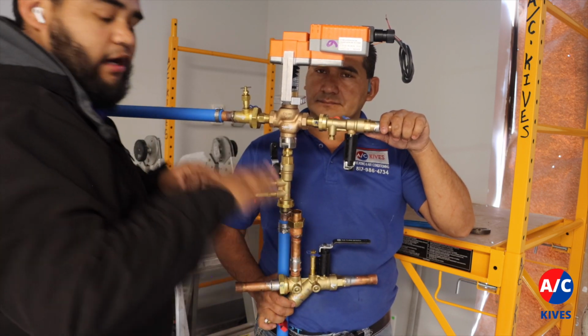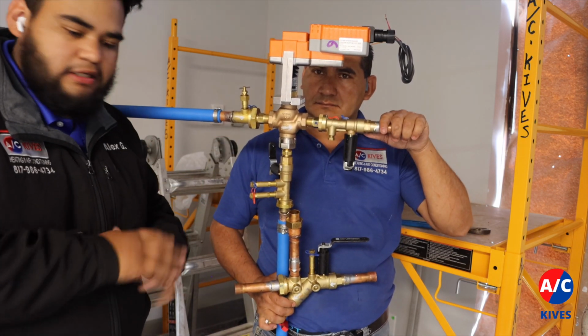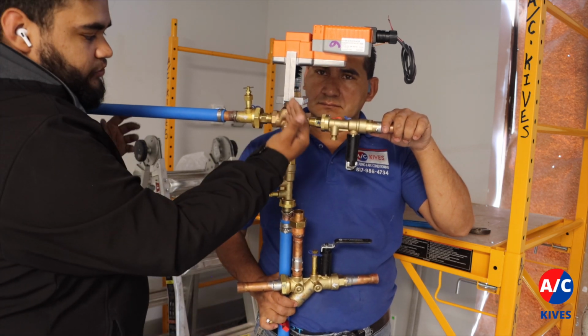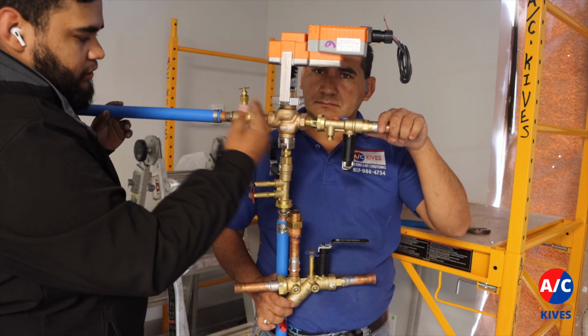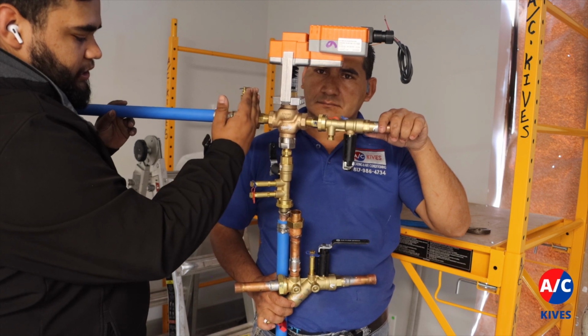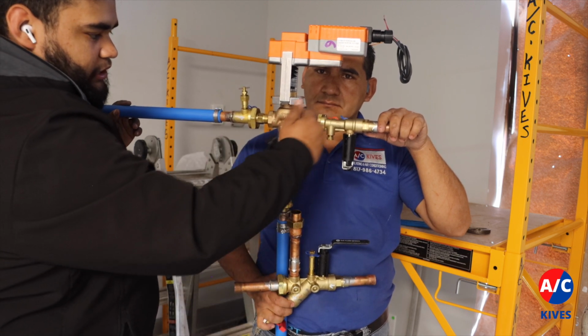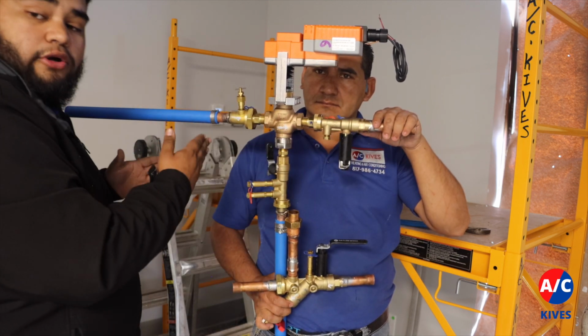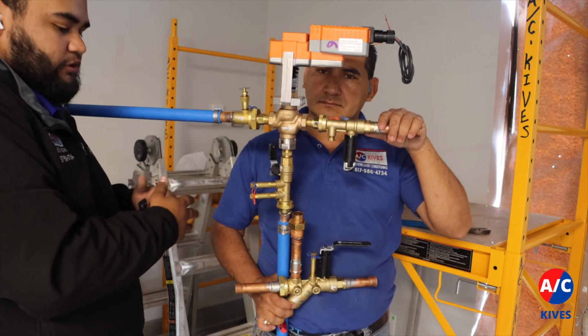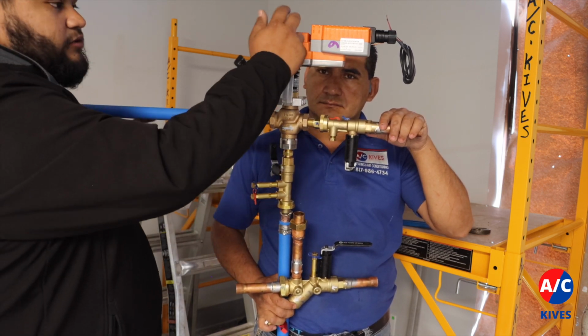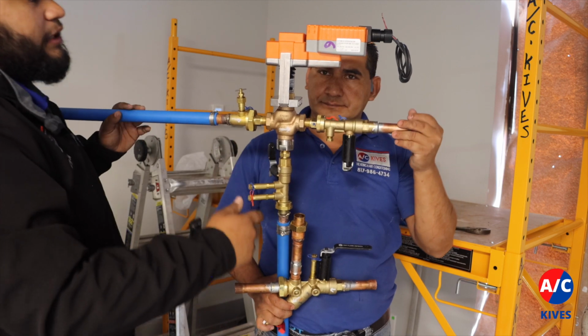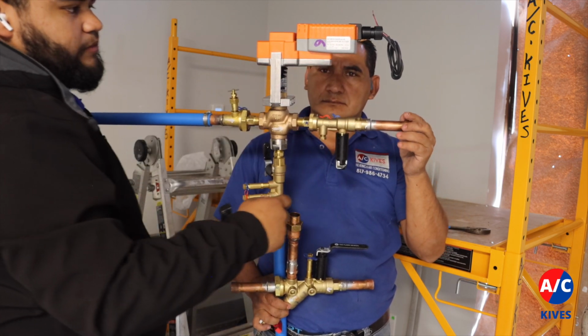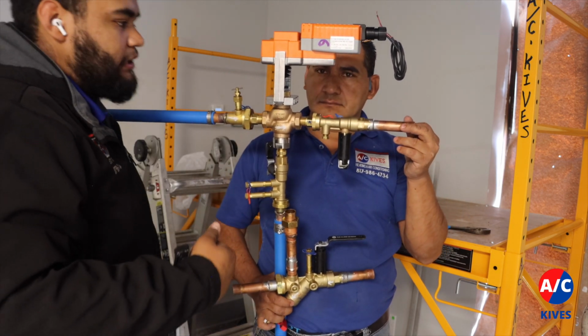But let's say it got to its set point and now it doesn't need to be turned on. The actuator is going to cover over here, so the water will stop right here and it'll keep going right here. So the coil is now not getting into a cold temperature and it's in the off state, and that's what the actuator does. The actuator also determines how many gallons per minute it does.